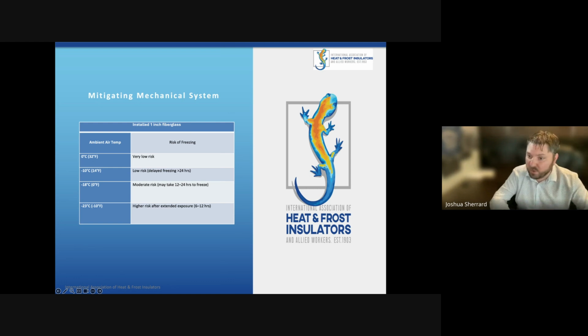As systems break down and temperatures drop in certain regions, we see cold water piping and chiller systems freeze, pipes burst, causing a lot of problems for clients. Just by maintaining that system and making sure 1-inch fiberglass is installed, you can see how the temperature drop is managed and the extended life for the system, or extended time for you to make maintenance changes, is greatly extended. I think it's very important that we're looking at that.